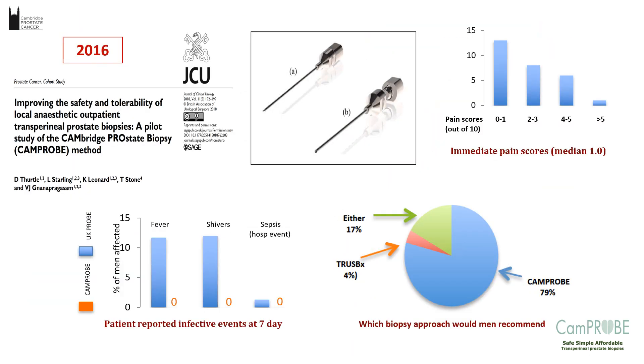We had a study in our hospital, and it was very interesting that because we developed and made the device in our hospital, we didn't need MHRA approval. We effectively showed it could be used safely to take prostate biopsies in a study of about 30 patients. Compared to transrectal biopsies, we had no fevers, shivers or septic events, pain scores were very acceptable, and patients who had previously had a transrectal biopsy much preferred the CAMPROBE approach. This pilot study, published in 2018 from a study started in 2016, showed proof of principle.